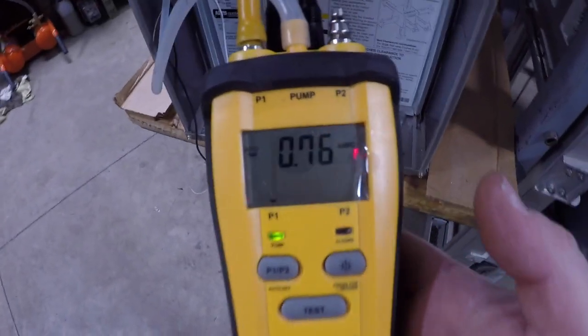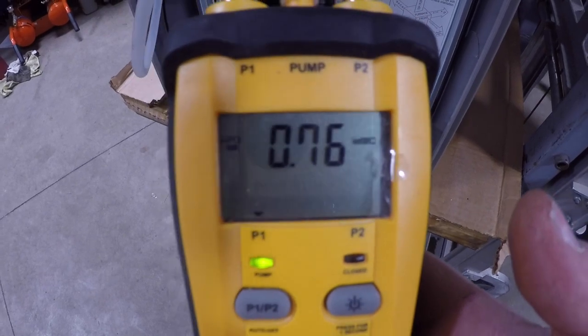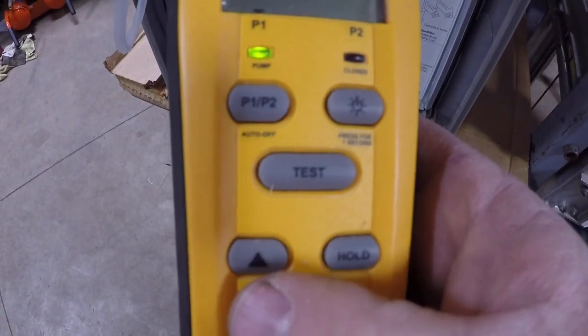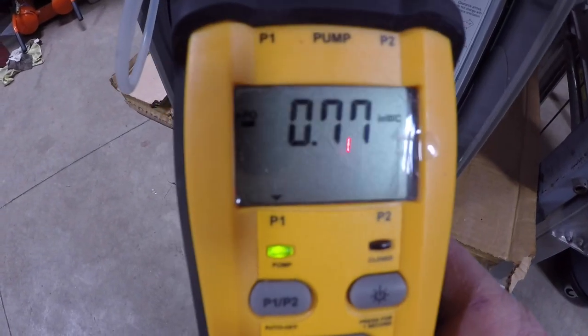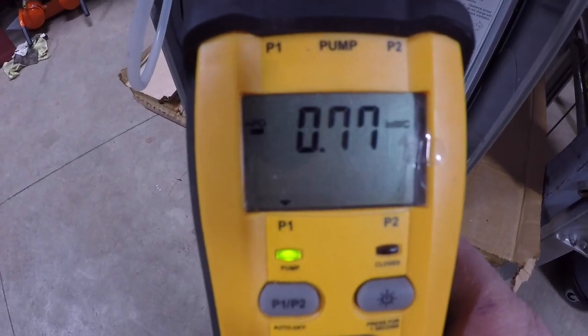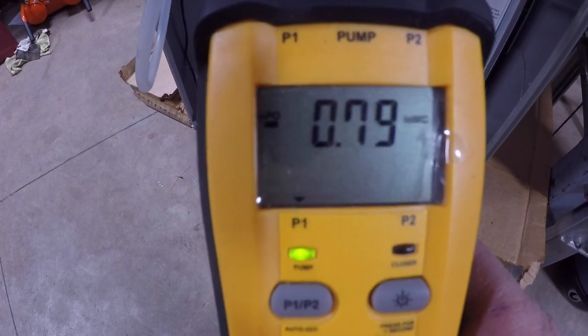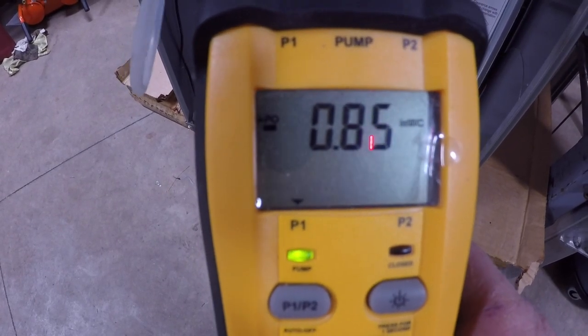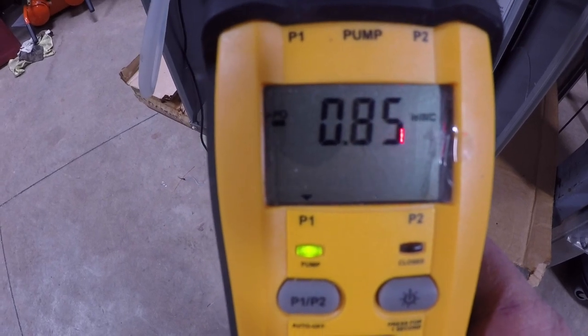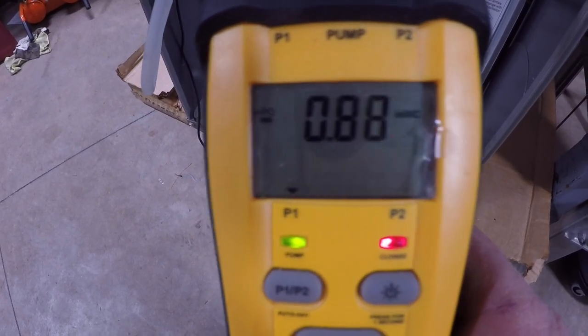I want to make sure that the switch is operating like it should, or if the switch is broken. So what I have here is this machine has a little pump built in, and I've got a couple hoses and 2 electrical leads, and I'm hooked up to the pressure switch. What I'm going to do is I'm going to start watching this little light here that says closed. I'm going to increase the pressure, or the vacuum that I'm drawing across that switch, to see when that closes. Now I'd verify where it's supposed to close, and I'm slowly increasing, and I know I'm getting close to where it's supposed to be. So just about there, and right there at 0.88 is actually where it closed.